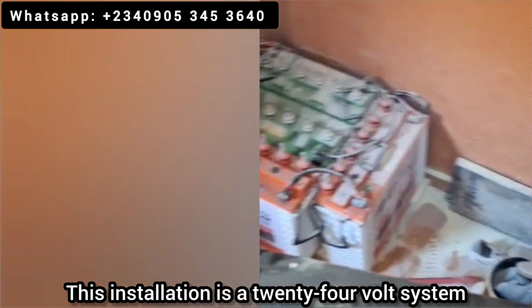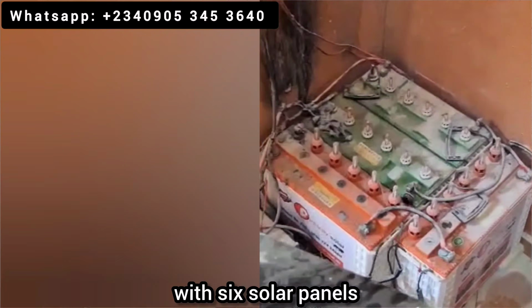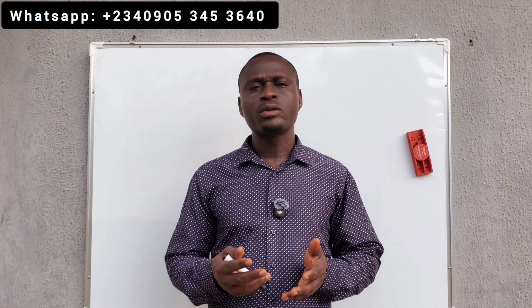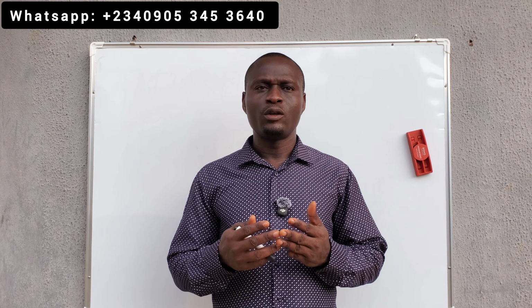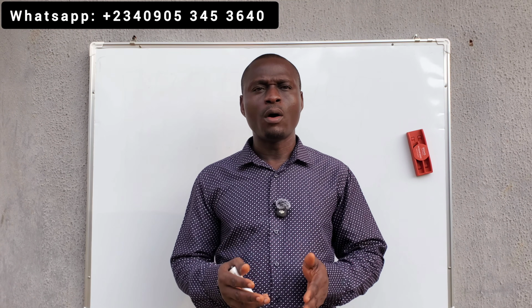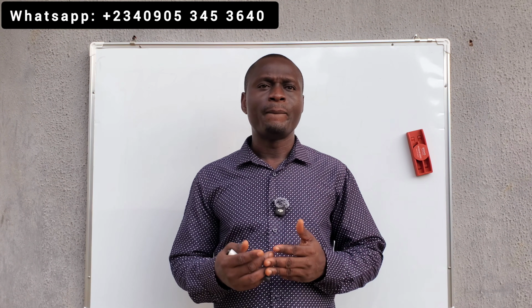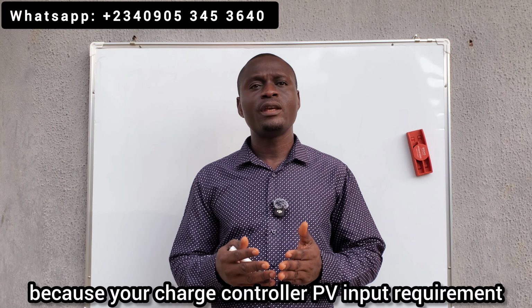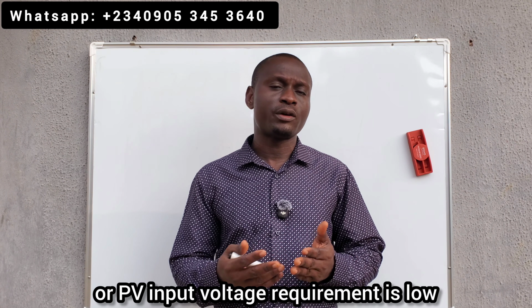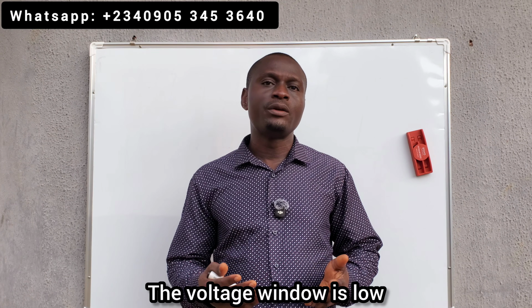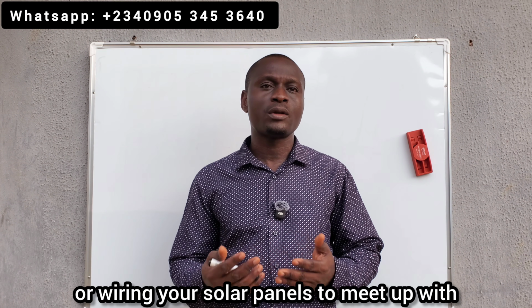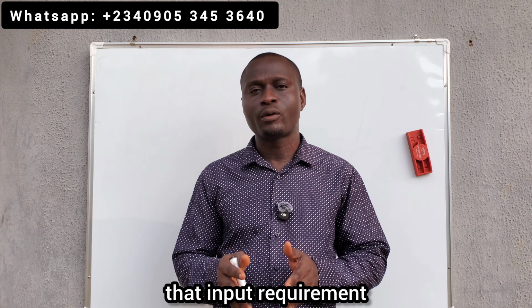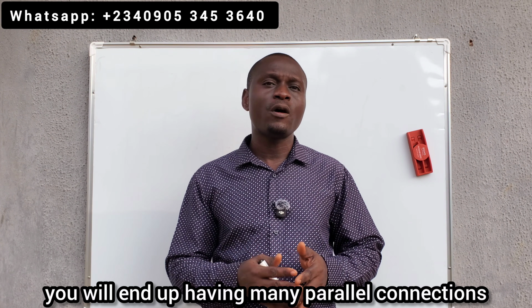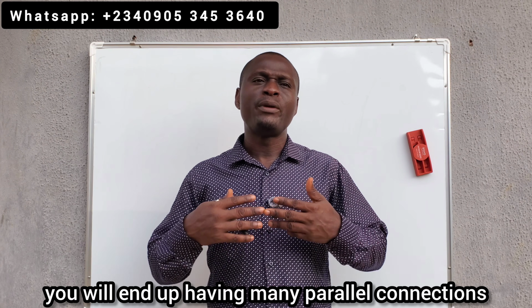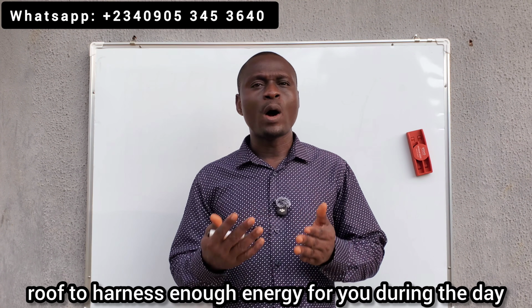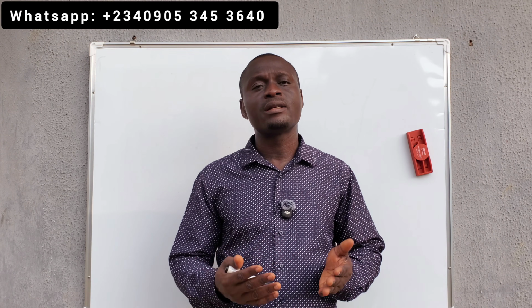This installation is a 24-volt system with 6 solar panels. If you have a low voltage system, most of your connections will be in parallel. You may have series parallel connection, but parallel connection will always be there because your charge controller's PV input voltage requirement is low. The voltage window is low, so you're always wiring your solar panels to meet that input requirement. As a result, you will end up having many parallel connections because you need enough solar panels on the roof to harness enough energy during the day when the sun is available.